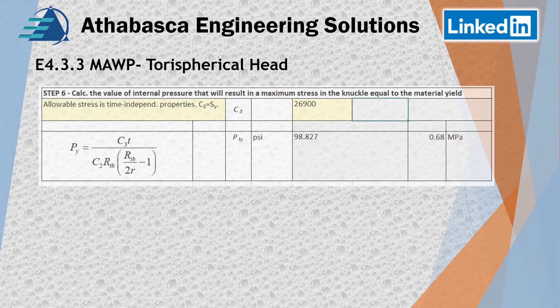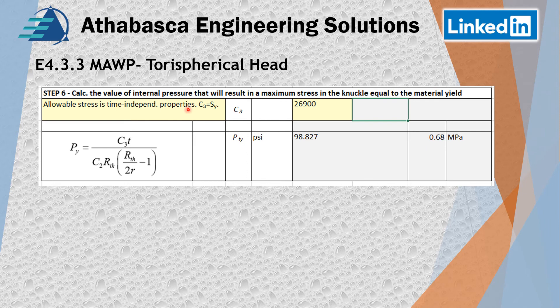In step six we determine a few other interesting variables — specifically, we calculate the value of internal pressure that would result in maximum stress in the knuckle equal to the material yield. We're only allowed to use time-independent properties for the code case. So we set C3 equal to the yield stress found earlier, put C3 into the calculation with the previously determined values, and at the end of the day we get 98.8 PSIG for that internal yield stress value.